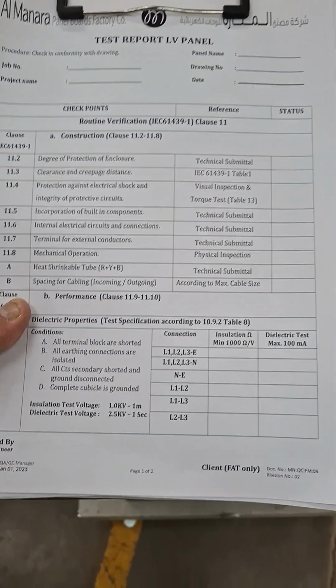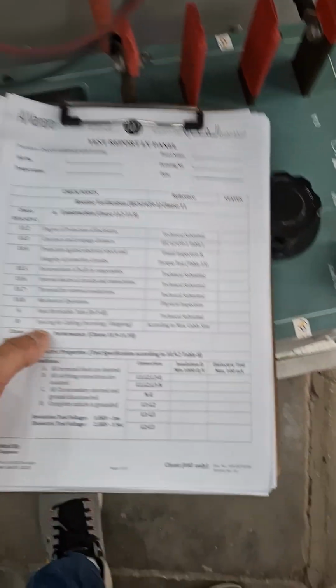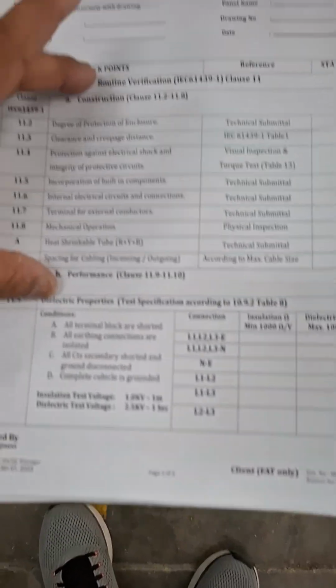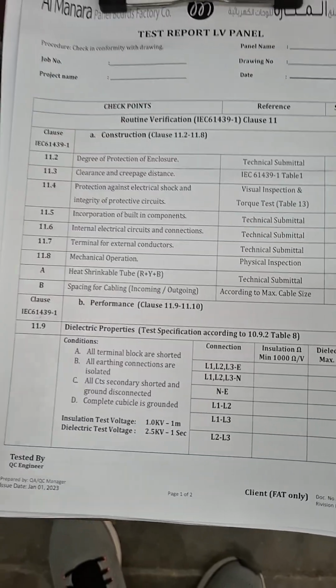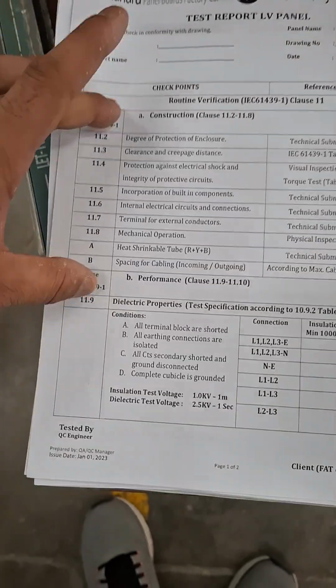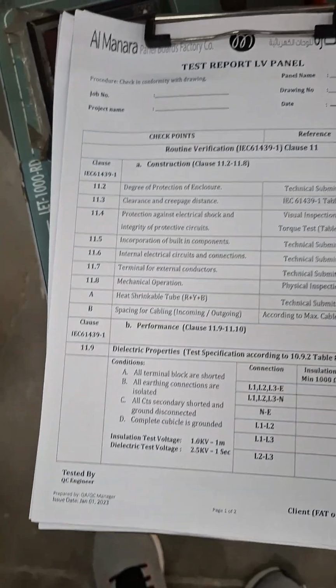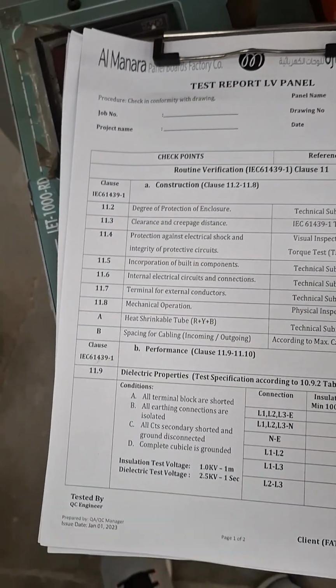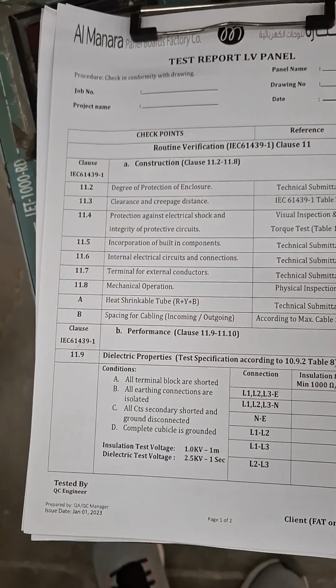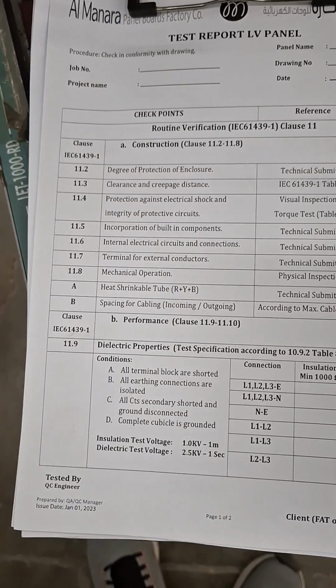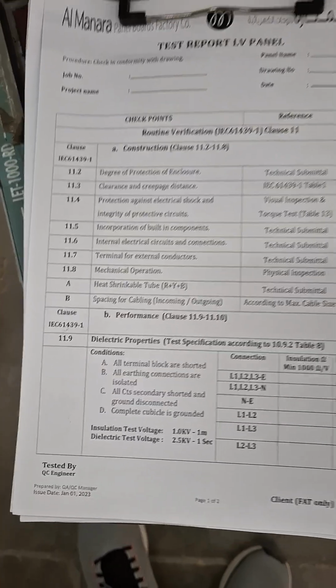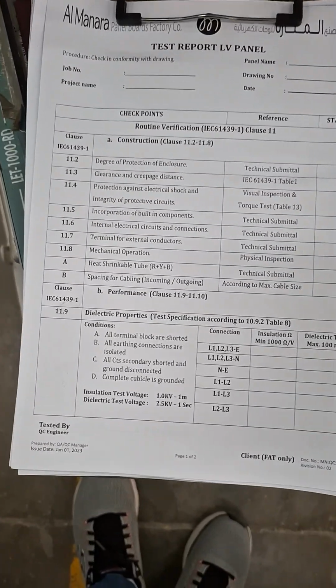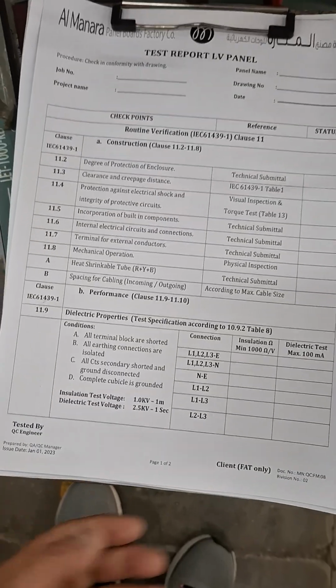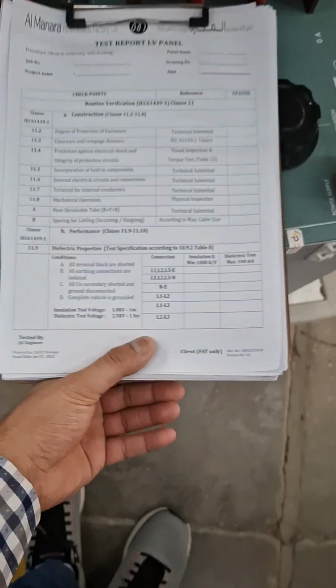This first part is our physical inspection. This part is physical inspection, which has some points: degree of protection, clearance and creepage distance, protection against electrical shock, incorporation of built-in components, internal circuit, terminal for external conductors, mechanical operation and tube, and incoming and outgoing cable space. Okay, this part has two tests.